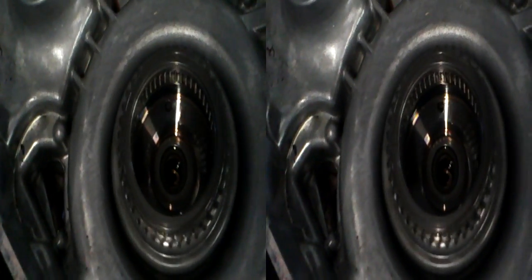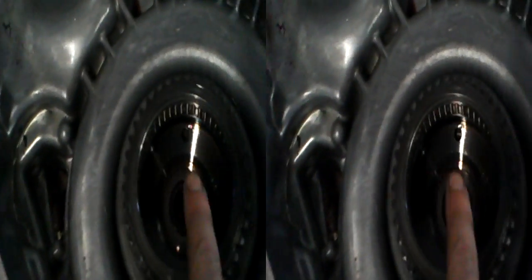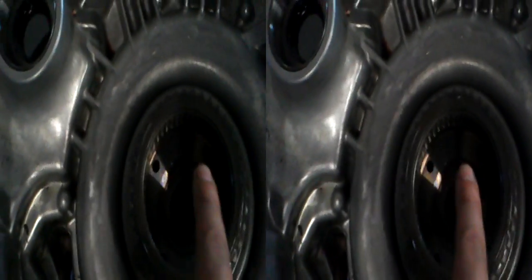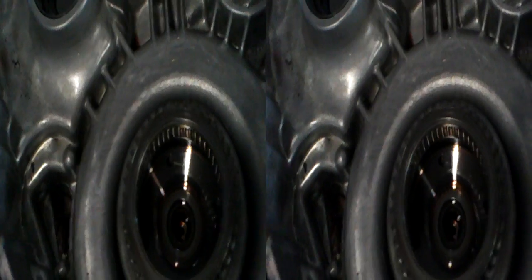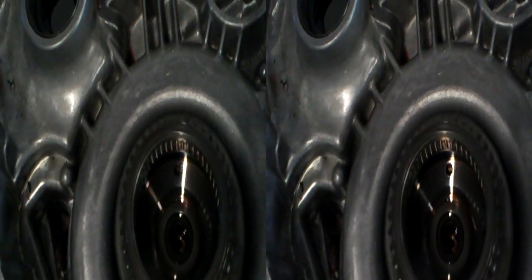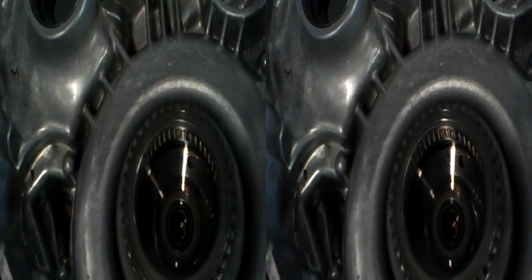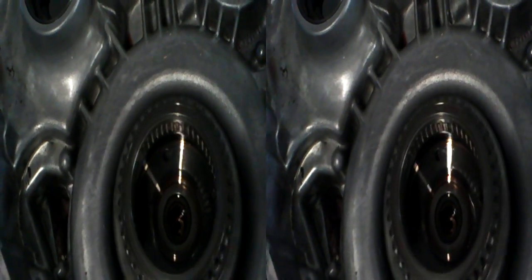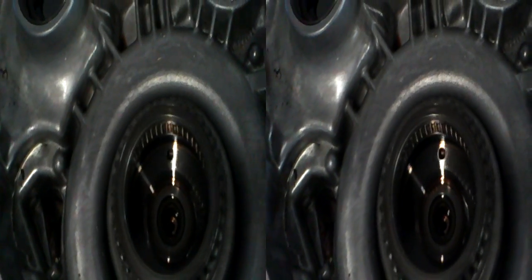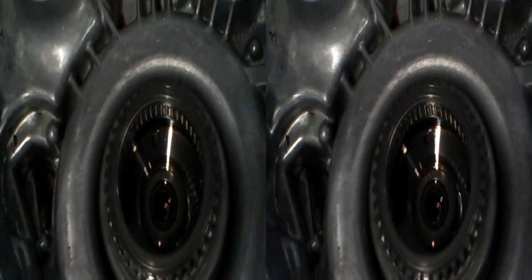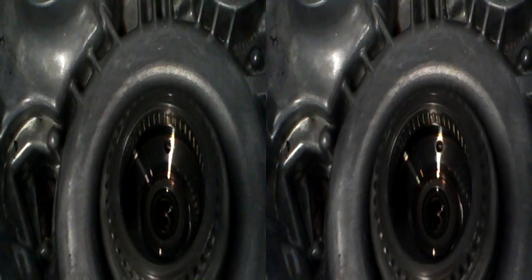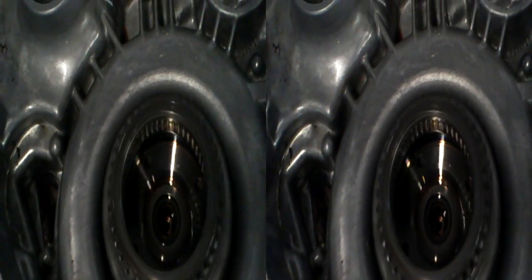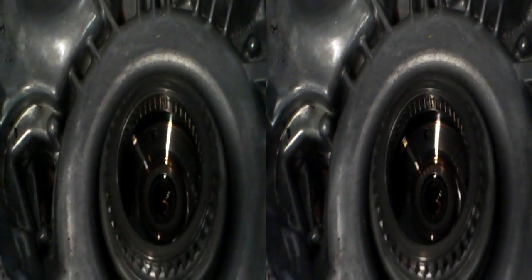There you go. One, two, three, four, five, six, seven, eight, nine. And you can see the hole. And basically, because it's four pole, if I get the reflection right, you should be able to see the hole passing, which will coincide because it's four pole. Each time that hole shows in the reflection, that's one pole there, that should be 12 clicks. Yeah, that sounds about right. I mean I'm not counting, but I can hear.